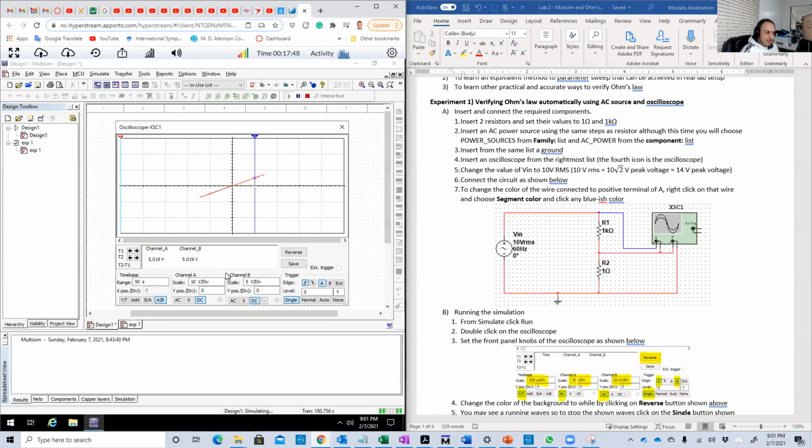Okay, millivolt. So if you divide now 5019 by 5.019 millivolt, this will give you 1000 again. Okay, and that's basically the trick. And that's why we chose in the first place R2 to be 1 ohm.